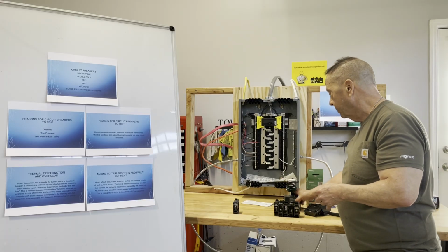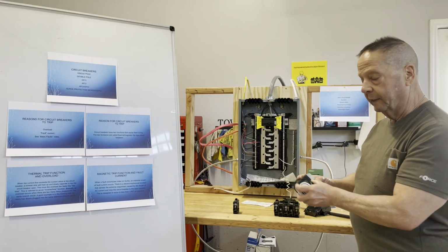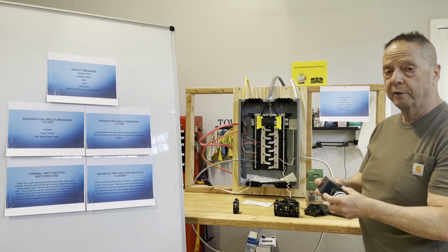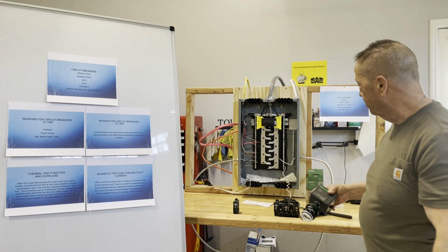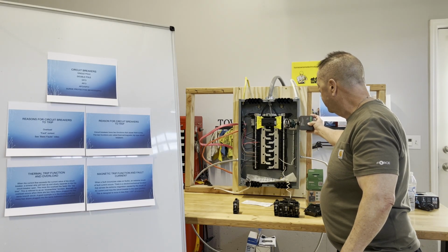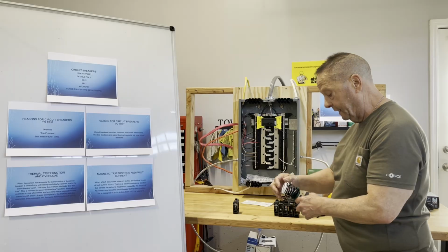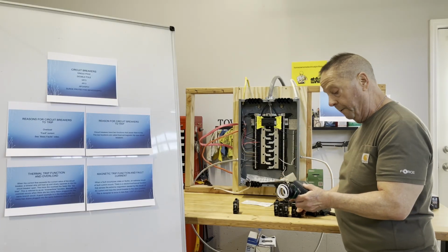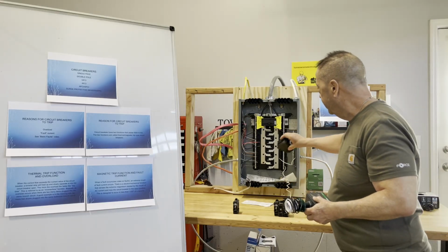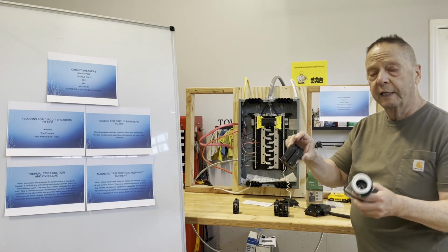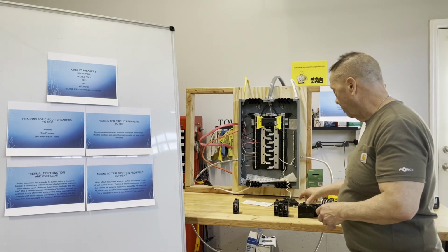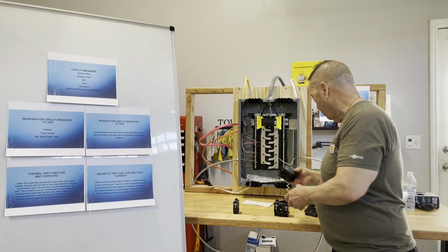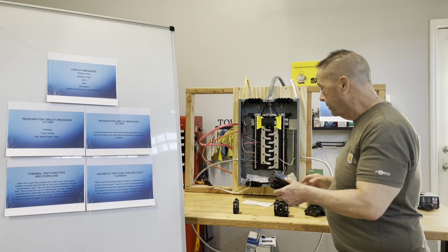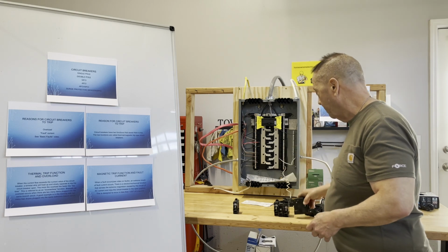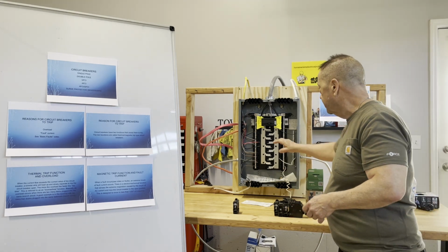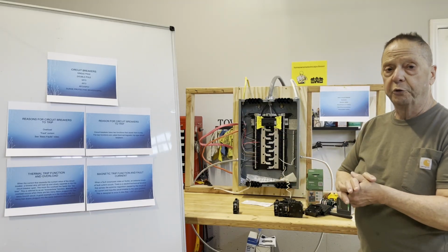Now there are also surge protective devices. Today's National Electrical Code requires them on new panels that are installed in residential units. There's really two types. One that mounts onto the side of the panel, and then these wires are connected, the white and the green are connected to your neutral bar, and then the two black wires would be connected to a 2-pole circuit breaker that's mounted in the panel. There's also one you can buy where it's all enclosed in the circuit breaker. This part here does not exist, and it would merely plug onto the electrical panel. The manufacturers of the surge protectors, they want it as close to the main breaker as you can get it.